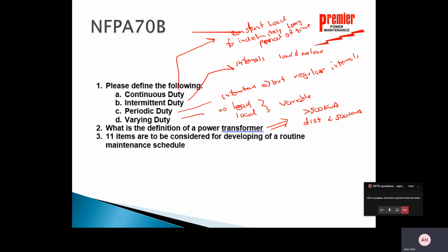Then item number 3. This is one of the big high points of NFPA 70B, is to develop routine scheduled maintenance. What are the 11 items considered for that? And I'll try to write these out in some sort of legible form for you. Number 1 is the potential for personal safety. So if there's something that could risk personal safety, that would be the highest level of concern for developing the maintenance program.